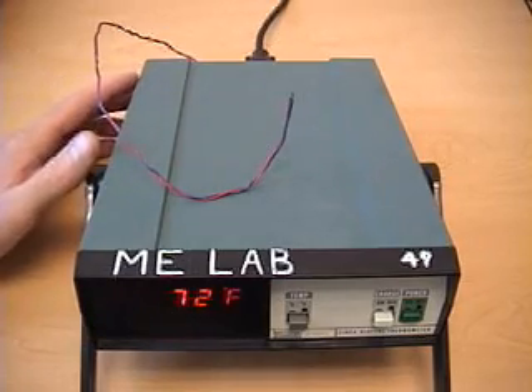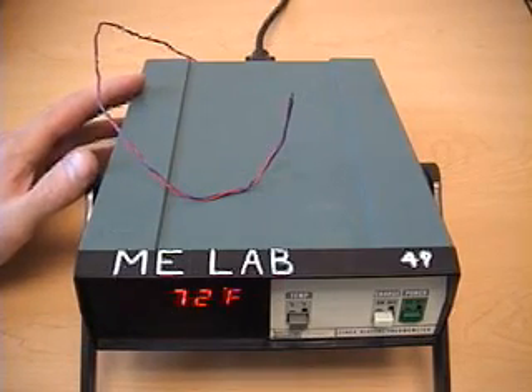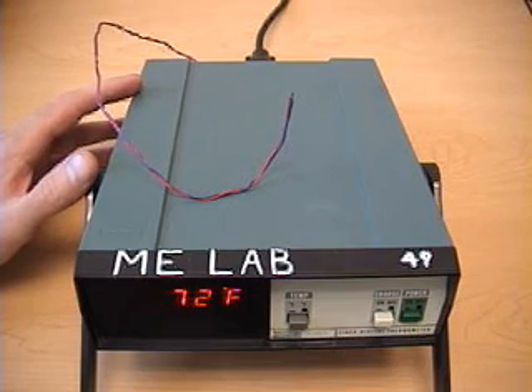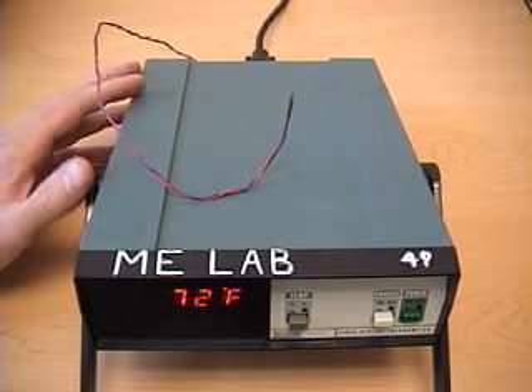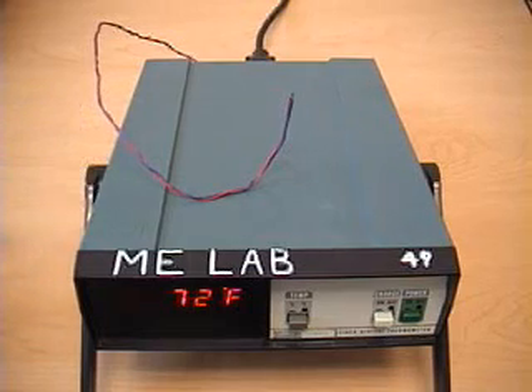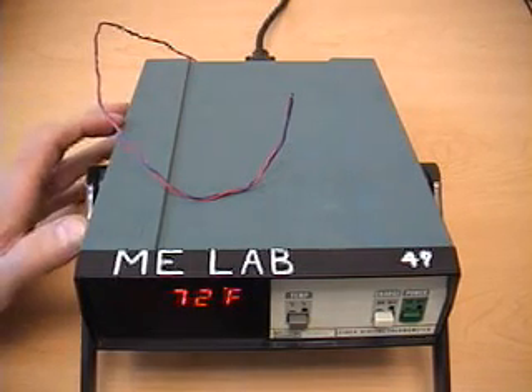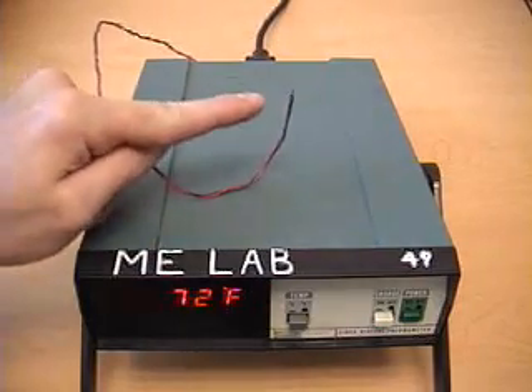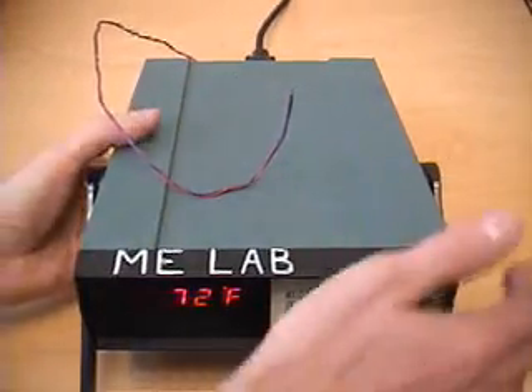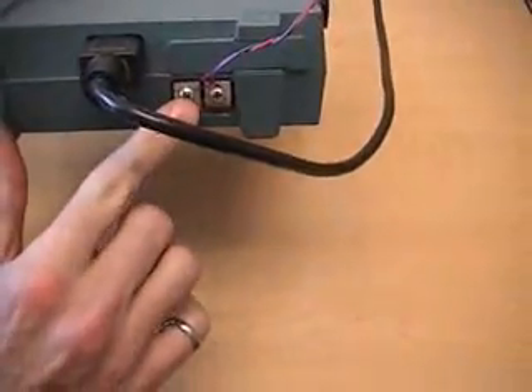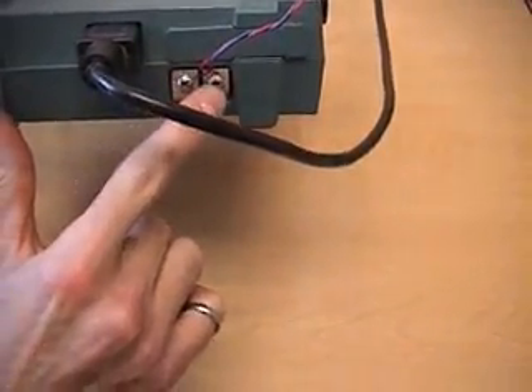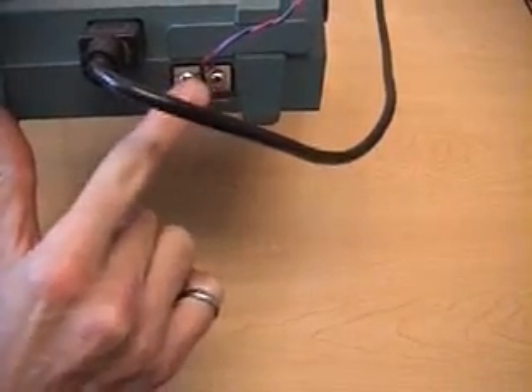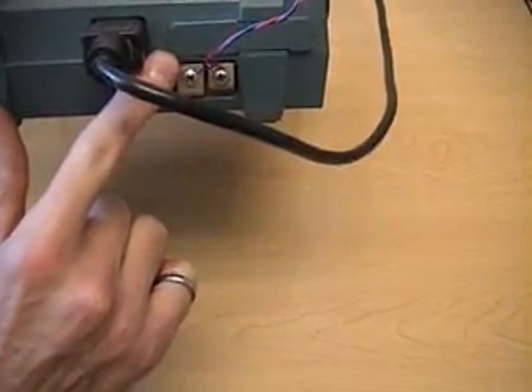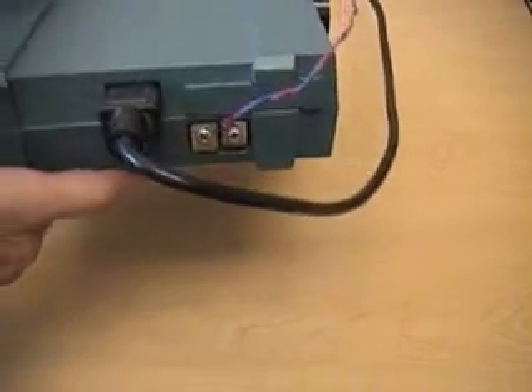Inside the instrument is the reference junction, and there's a temperature compensation circuit that adjusts for the temperature of that internal junction using an integrated circuit temperature sensor. So that's all internal to the device. So we have the external junction used to measure temperature, and on the back of the device, where the two wires are attached, there's two junctions here, but they're at the same temperature and their effects cancel. And again, inside the device we have the temperature reference junction.